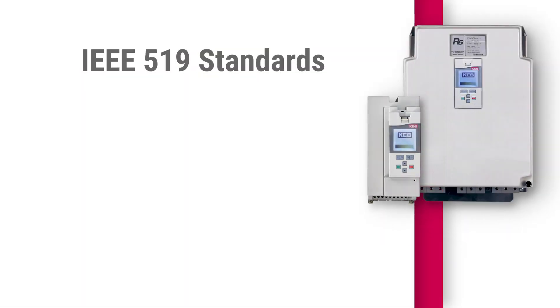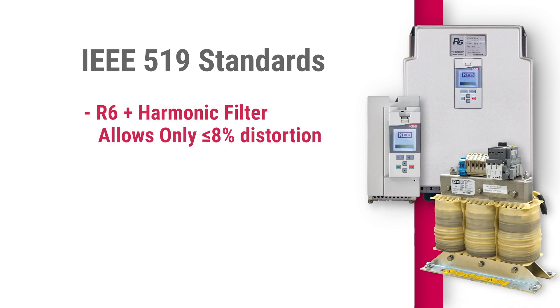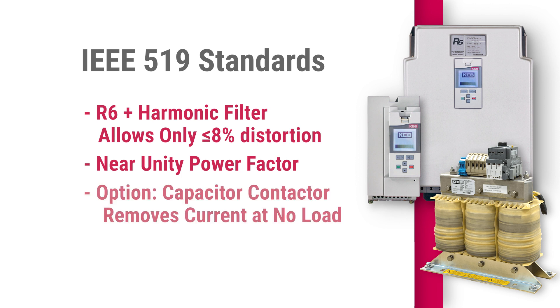Now we'll talk about how our harmonic filters meet the IEEE 519 standard. Pairing the regen and harmonic filter together can achieve less than or equal to 8% harmonic distortion. We can also provide near unity power factor, which means most power transfer is usefully consumed by the load. An option we can include is the capacitor contactor, which removes the capacitors while at an idle state, eliminating the capacitive current at no load.